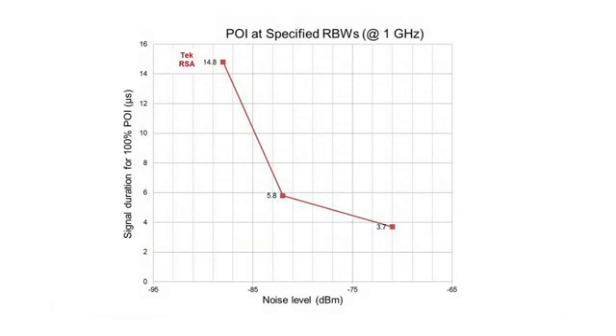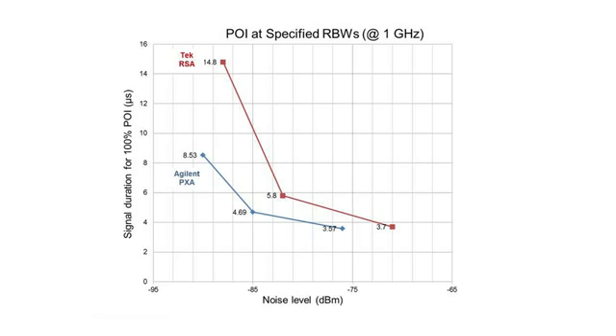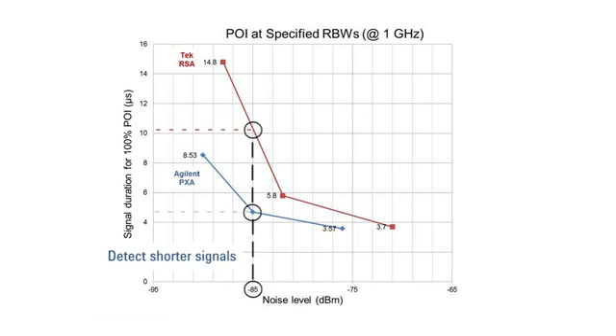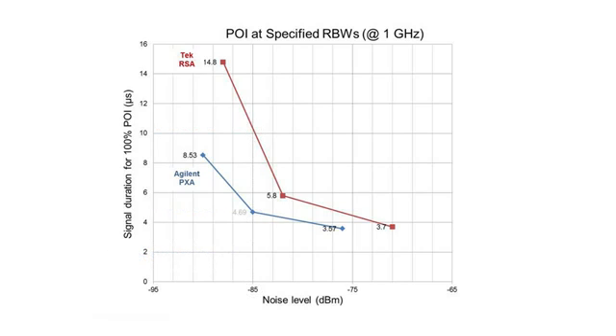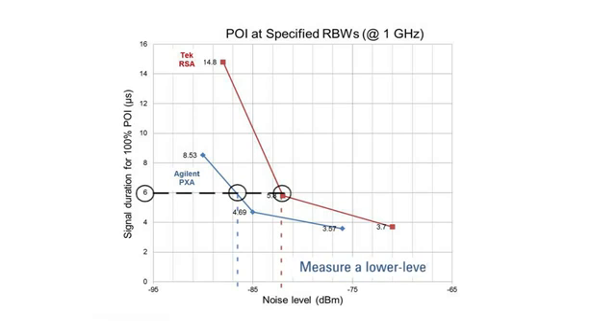I measured the noise level of the Tek RSA at three specific RBWs. At the same RBWs, I also recorded the POI spec from the RSA's data sheet. I did the same with the PXA. This graph shows the PXA and RSA's minimum signal duration POI spec at each noise level. You can see that at a given noise level, the PXA can detect shorter signals than the RSA, or in other words, has a much better POI at a specified noise level. Another way to look at this is that for a specific signal duration, the PXA is able to measure a lower level signal.